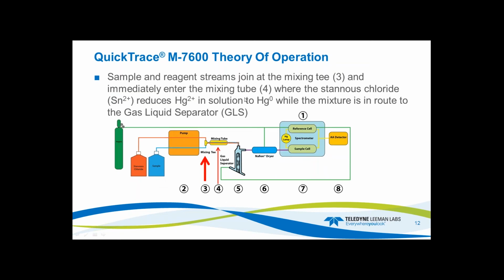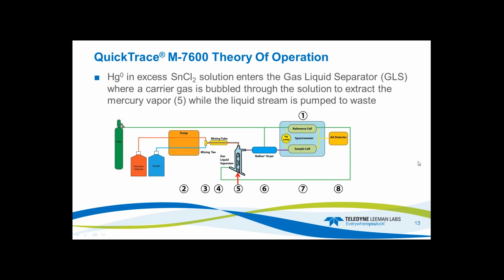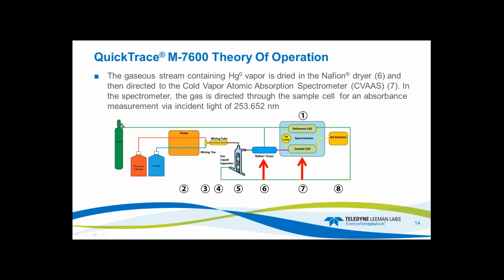The sample and reagent streams then join at a mixing tee, and immediately after the mixing tee, they enter a mixing tube reactor, where the stannous almost instantaneously reduces the Hg2+ to Hg0. That's happening while it's en route to the gas liquid separator. So then the Hg0 in excess stannous chloride will enter the gas liquid separator, and the carrier gas is then bubbled through the gas liquid separator to extract the mercury vapor, and then the waste stream is pumped to waste. So the gaseous stream of Hg vapor is dried with a Nafion drying membrane, and then it's directed to the atomic absorption spectrometer cell, which is the sample cell, and the gas is directed through that cell, and the absorbance again is measured at 253.652.